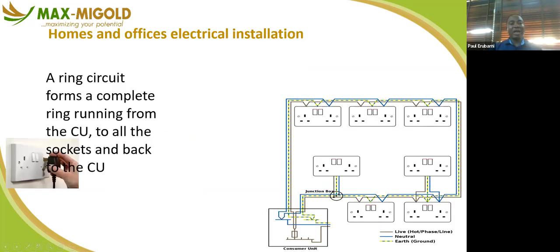So in installation, we have two types: the ring circuit installation and the radial installation. They each have their own advantages and disadvantages. The ring goes in a loop, so if there is a problem with one point, it affects the other. While with the radial, the distribution is taken from the distribution board directly to where you want to use it, like your cooker in the kitchen. You are not expected to join or combine a cooker with another breaker in your distribution board. You run directly from the distribution board to your kitchen.